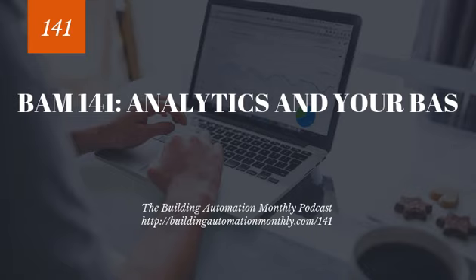So you can see this in some of the more advanced analytics solutions that are out there. Now, it's important to determine where the analytics are going as far as where they're being installed. Are you installing them on a new building or an existing building? This looks quite different depending on what kind of building you're installing analytics on. On new buildings, our primary concern is making sure we get the right points mapped in and we get the right data nomenclature up front. We get our data normalized up front. We collect the right amount of data at the right intervals, and we pull it into our analytics solution.